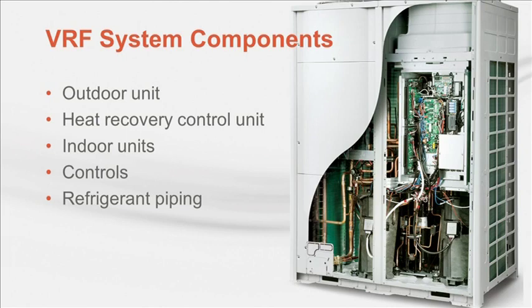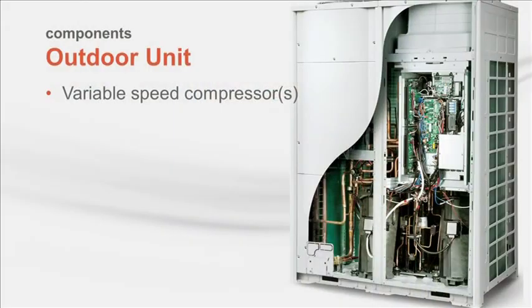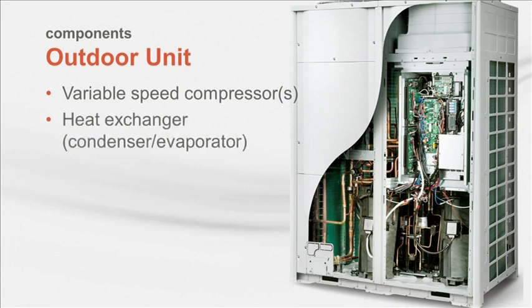First, let's spend some time looking at the outdoor unit, its components, and how it works. The outdoor unit typically contains one or several compressors. Because there are multiple indoor units with changing loads and usage, variable speed control is used to vary the amount of refrigerant flowing through the system. Today, most units contain at least one variable speed compressor to provide modulation. The name variable refrigerant flow comes from this ability to modulate the rate of refrigerant that flows through the system. The outdoor unit also contains a heat exchanger, which serves as a condenser in the cooling mode and an evaporator in the heating mode, and heat rejection fans.